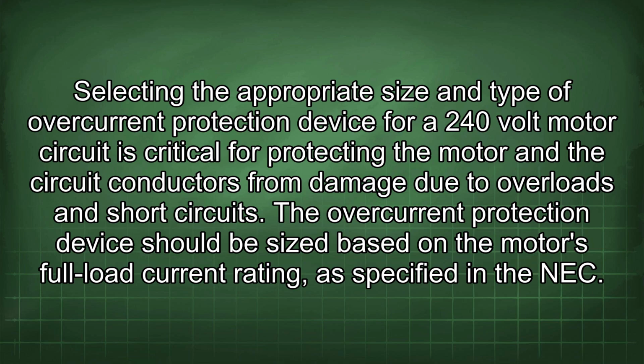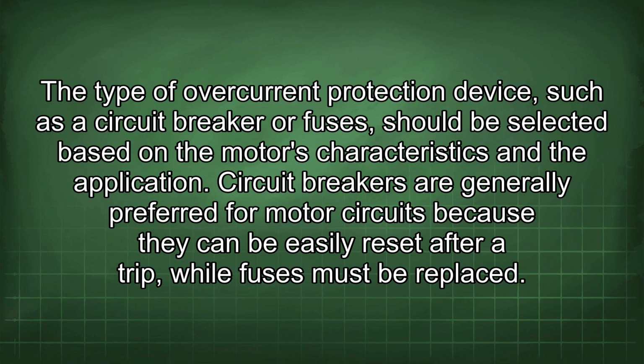Selecting the appropriate size and type of overcurrent protection device for a 240-volt motor circuit is critical for protecting the motor and the circuit conductors from damage due to overloads and short circuits. The overcurrent protection device should be sized based on the motor's full load current rating, as specified in the NEC. The type of overcurrent protection device, such as a circuit breaker or fuses, should be selected based on the motor's characteristics and the application. Circuit breakers are generally preferred for motor circuits because they can be easily reset after a trip, while fuses must be replaced.